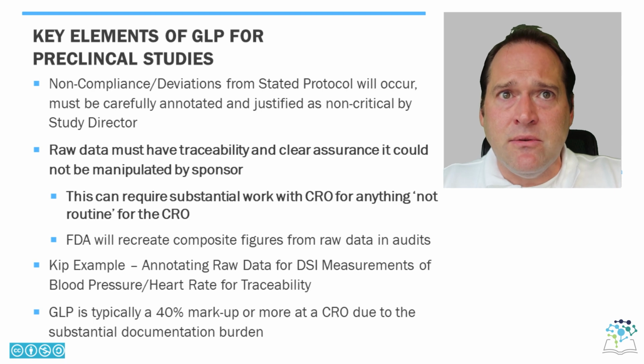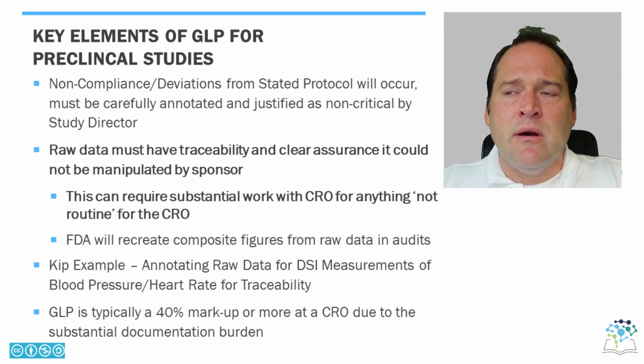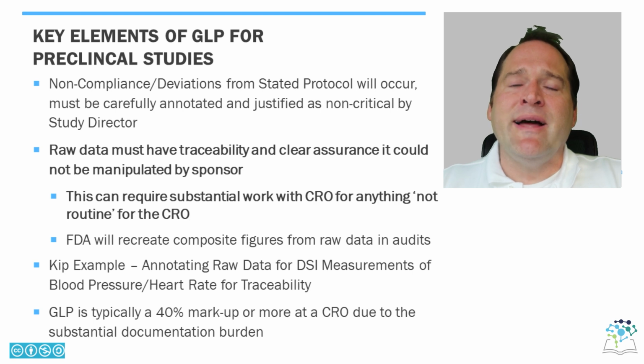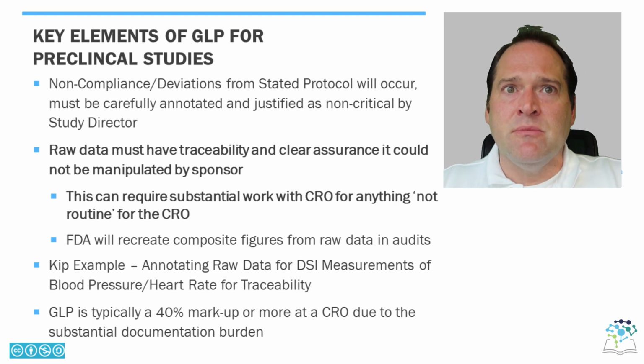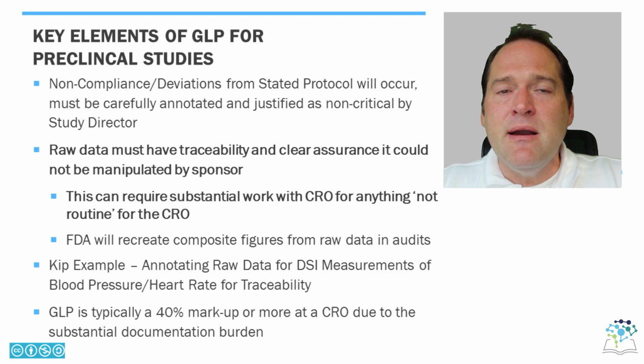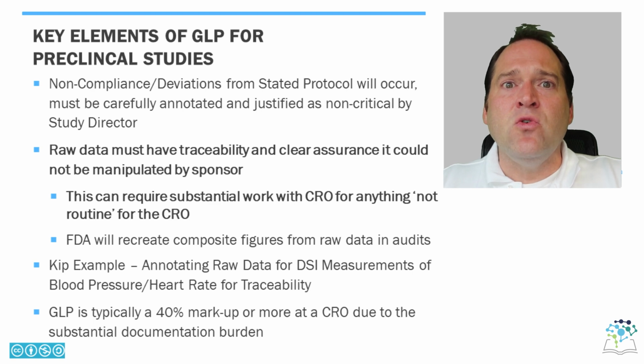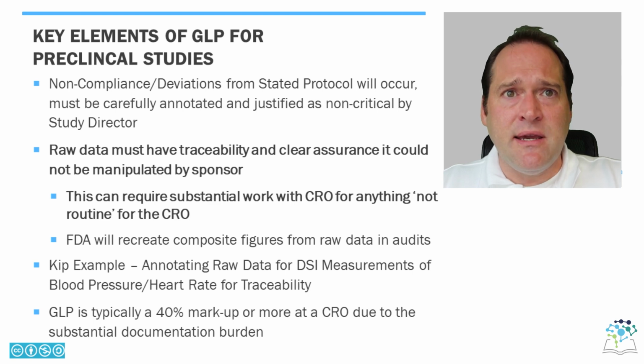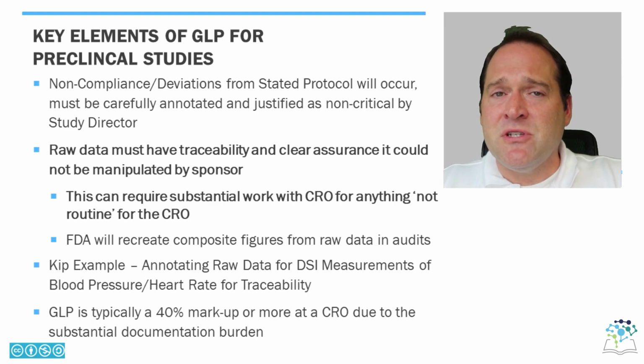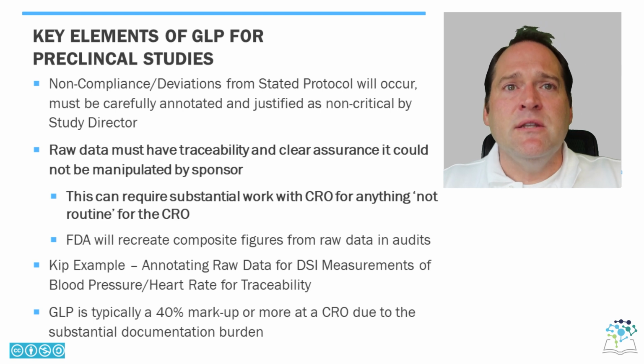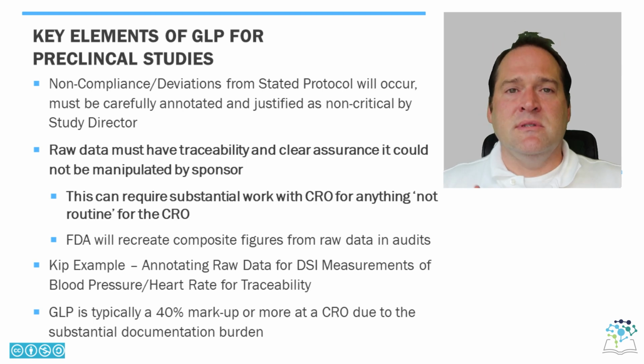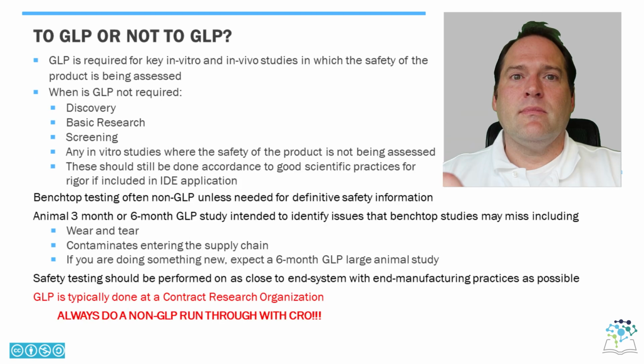And so in my particular example, when we were doing things for hypertension and heart failure, where we were doing implantable wireless catheter systems to measure blood pressure and heart rate, we actually had to come up with a way, with the manufacturer and the CRO, to store the raw data daily, annotate it, and lock it for traceability, so that they knew we as the sponsors could not manipulate it. Because this is actually much more complicated than a standard study, GLP is typically a 40 to 50% markup at a CRO versus a non-GLP study, due to this substantial documentation burden, with daily annotation of the data in many cases.